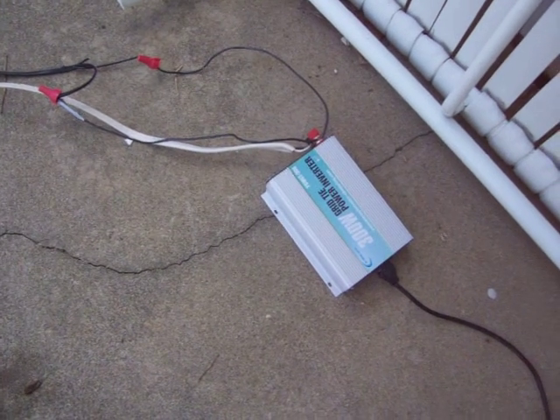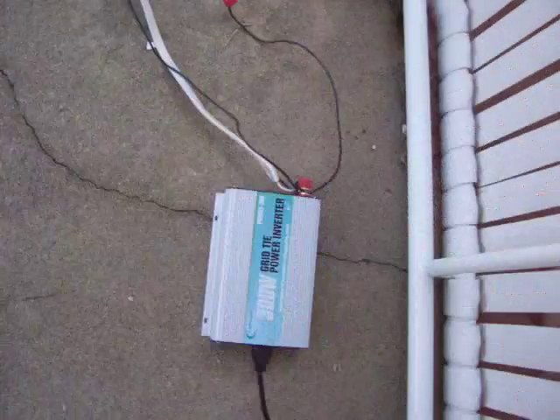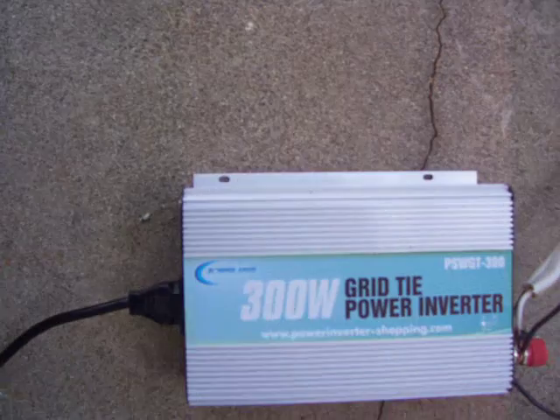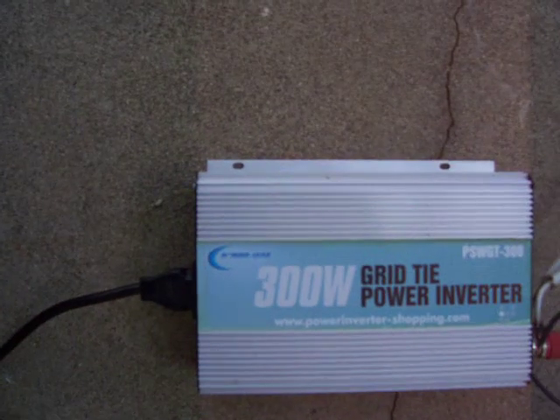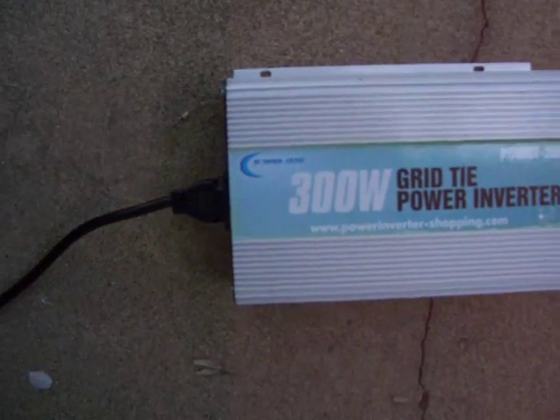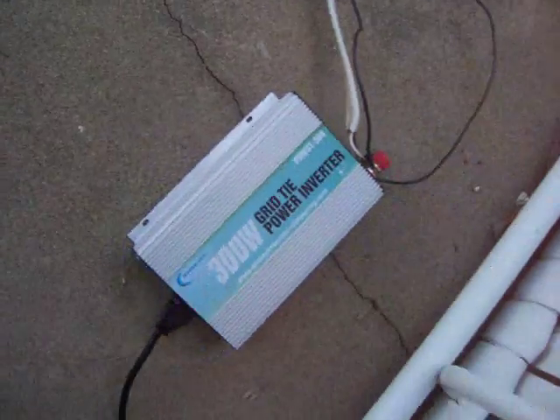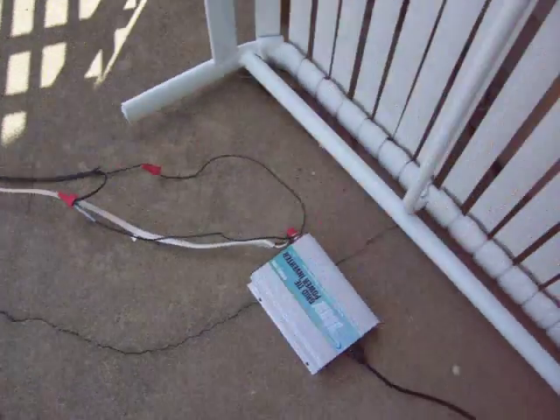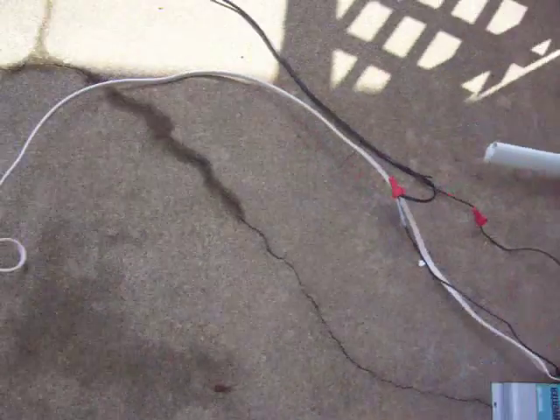It works pretty good. This thing is called the PSWGT-300 grid-tie power inverter — it's called the Power Jack. They say it's 90% efficient, but the way I calculate it, it looks like it's about 85%, so I'll take the 85.